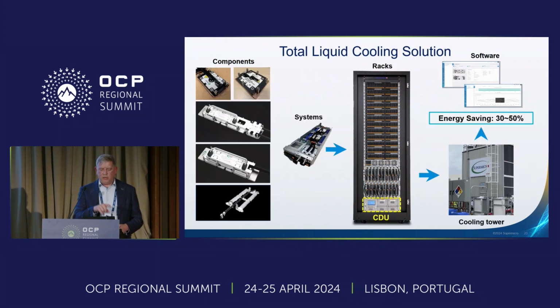We have a total liquid cooling solution. It can work all in one Supermicro system, or you can mix and match vendors at any point—we do that all the time. We have components and systems, and we can take it to the rack, fill it with a CDU, bring in a cooling tower, and bring the software to integrate it all. The software works with almost all the other competitors and collaborators out there. Our goal is to find energy savings of 30 to 50% for our customers.